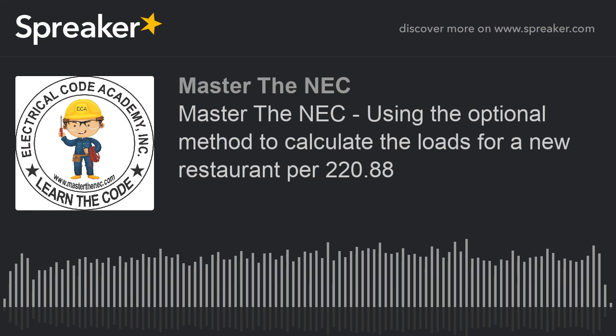And we have service conductors coming in from the utility into this panel. Now, if it comes into this panel and then this is the final destination of those service conductors, and now I've got multiple feeders coming out to other panels or potentially branch circuits going out to other panels, then I can do this. I can use this optional method for the service load calculation, but I can't use it for any of the subsequent feeders that are coming out of it.